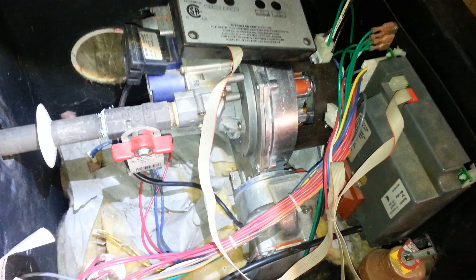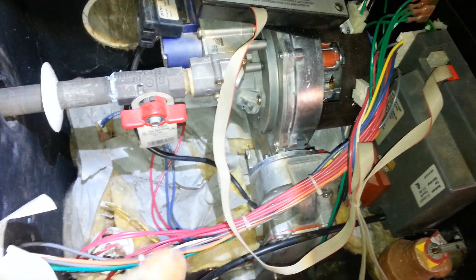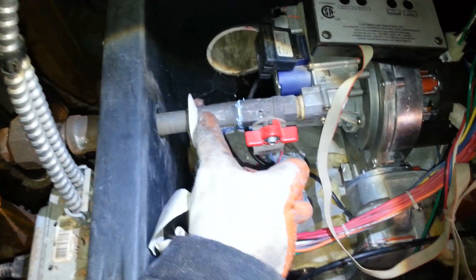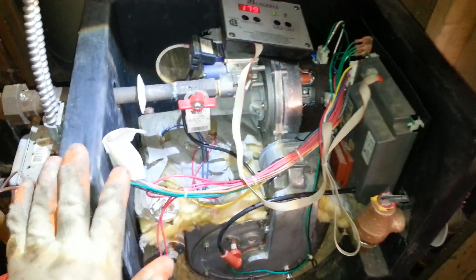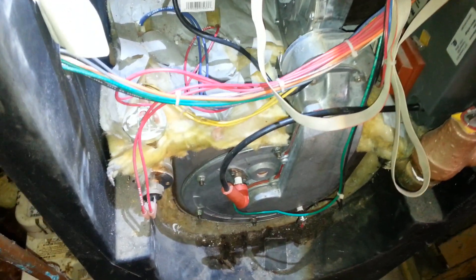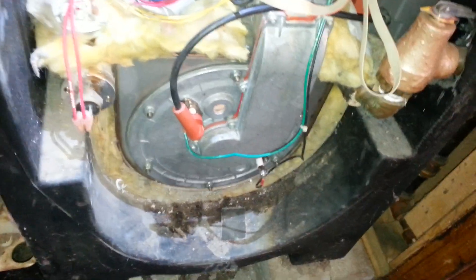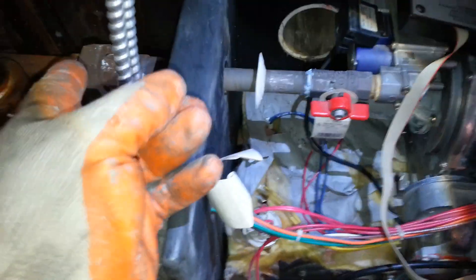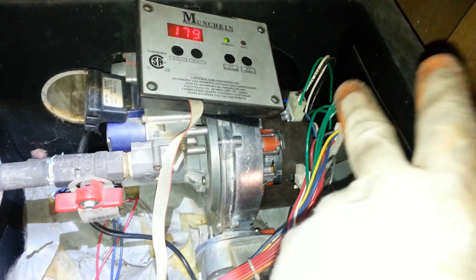It's a little tricky to replace. First of all, you would have to shut the gas off. In this application, we'd have to shut the gas off, take this union apart, and take this nipple out so that we could remove this whole thing. There's really not a lot of working room on these, as you can clearly see — they're aptly named the Munchkin for a reason.